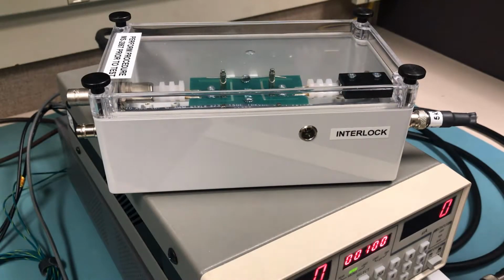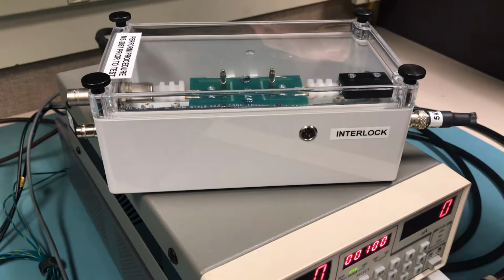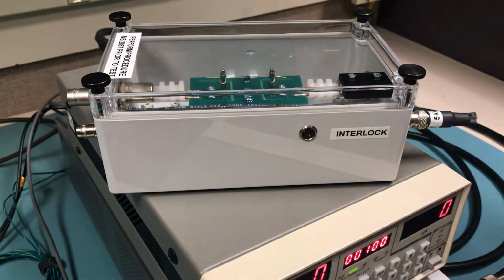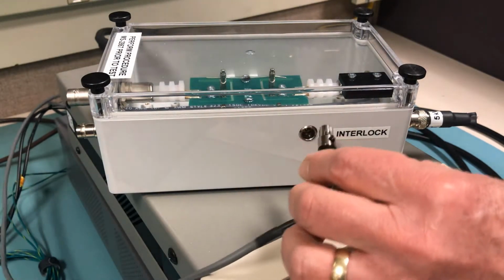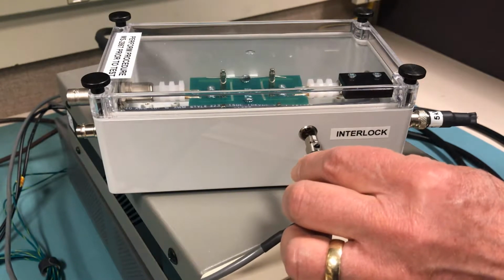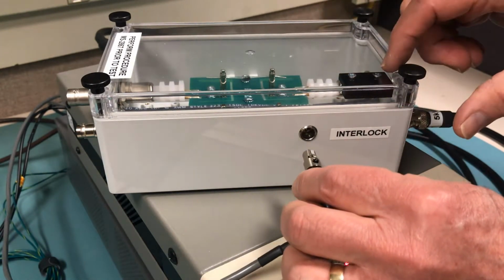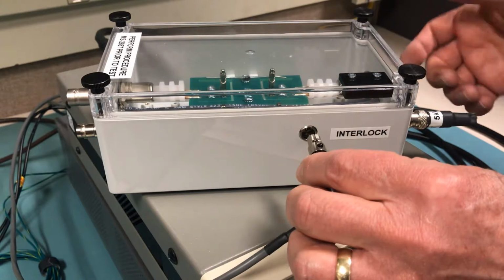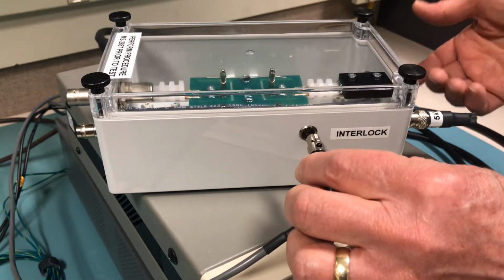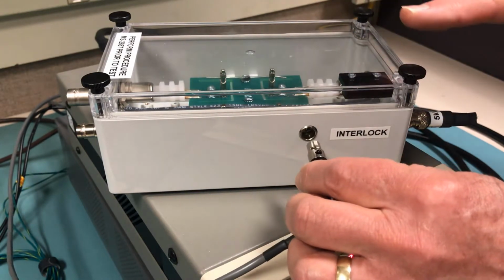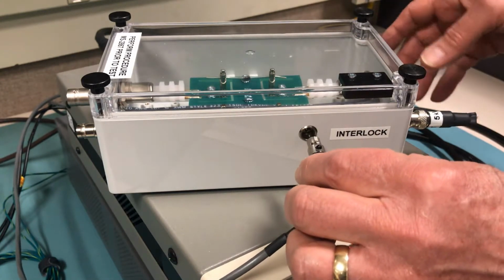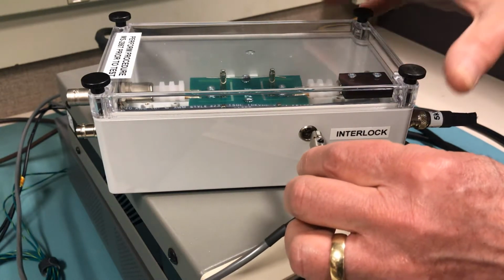Now for safety, I need to run the interlock cables from the instruments, from the high voltage power supply and from the source meter, into the test fixture, and this one cable combines those two interlock connections. The proximity switch on the top of this fixture ensures that the top has to be on the fixture before we can apply any voltage.